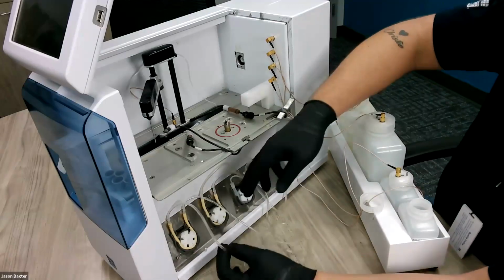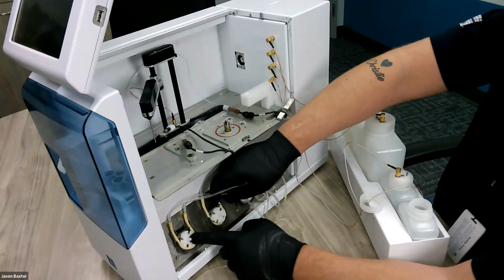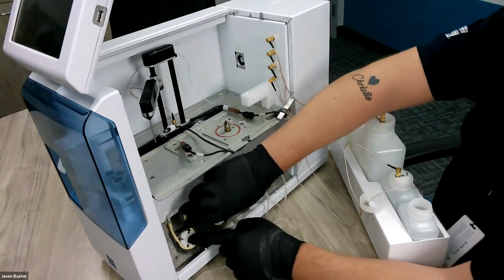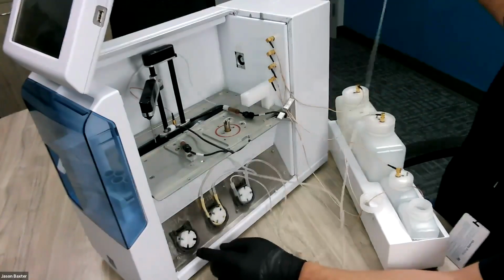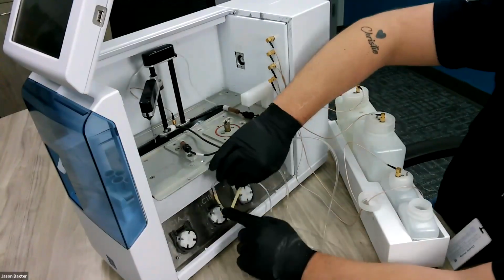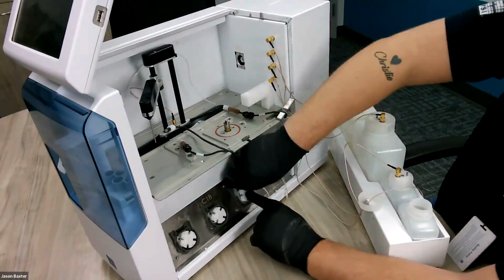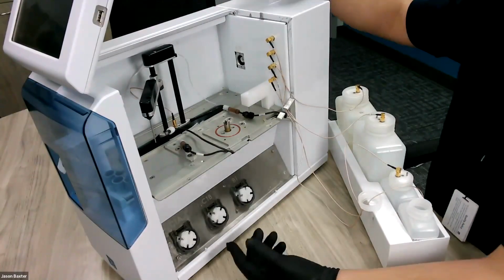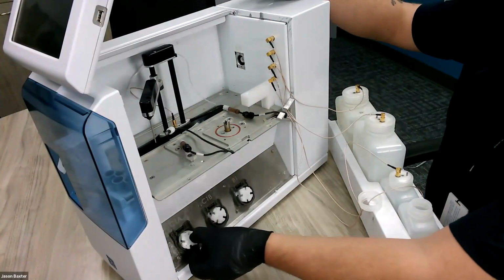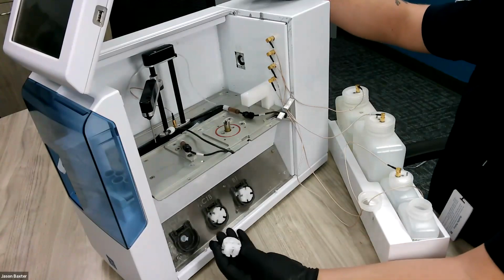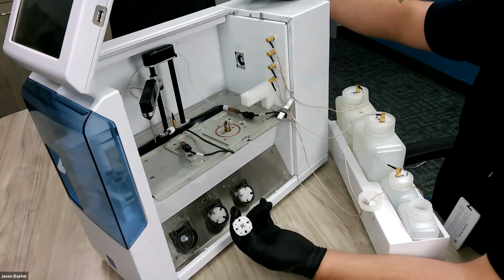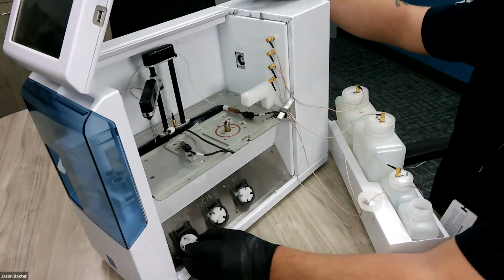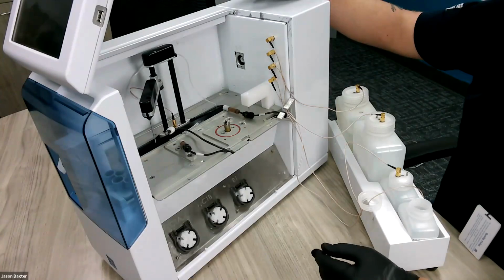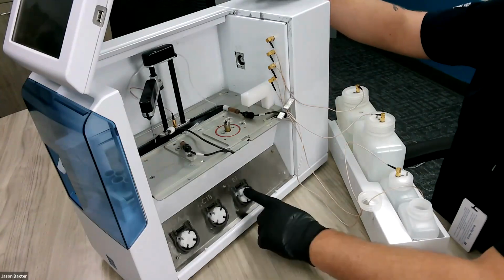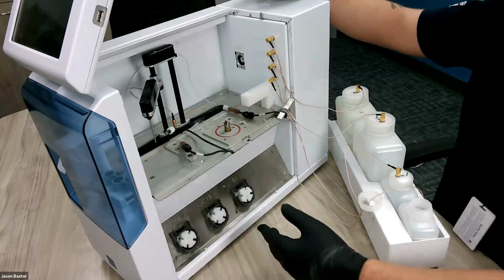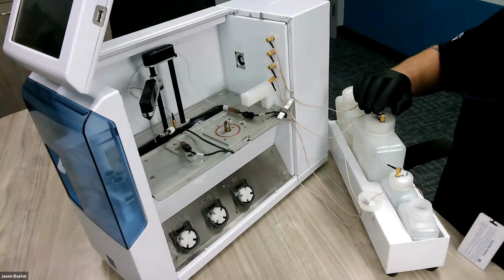So once you have your gloves on, you simply grab hold of the tubing. I put an index finger on the peristaltic wheel, the white part in the middle, and then I just pull that out, discard, pull this out, discard, pull this out, discard. If during removal you pull one of these peristaltic wheels out, no great deal. They just sit on a plus sign insert into the actual pump body. So all you have to do is just set them back in. The only thing holding them in is gravity. And all three of the wheels are the same. So if you pop all three of them out, you don't have to worry about which one goes where.